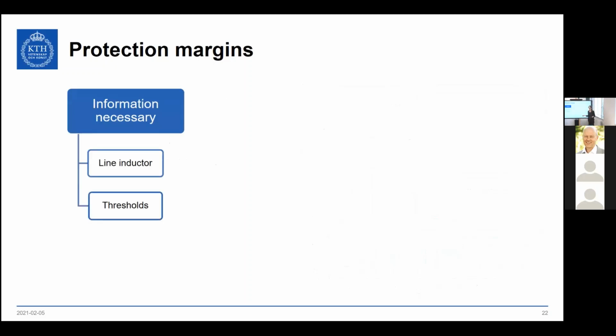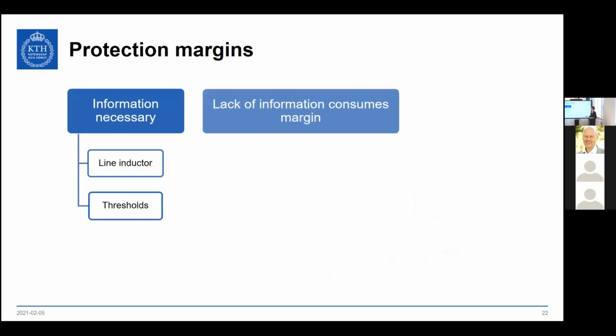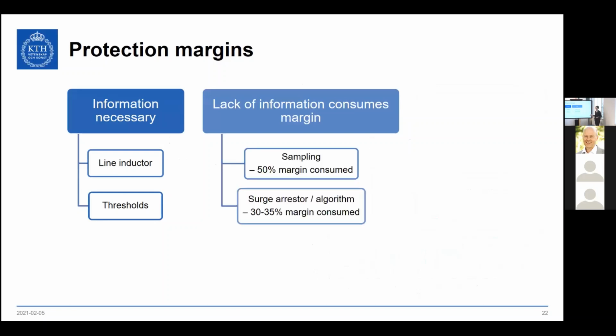I iterated through several aspects, and what I find is that it's really necessary to share information about the line inductor sizes and thresholds in such a setup. The lack of information consumes quite a large portion of the margin. For example, the sampling of the fault detection consuming up to 50%, or the surge arrestor curve in combination with certain algorithms consuming 30-35% of the margin. I didn't see a malfunction, but this is a warning sign if you consume 50% of the margin by not knowing this kind of aspect.